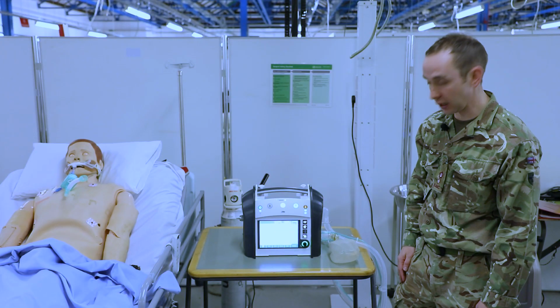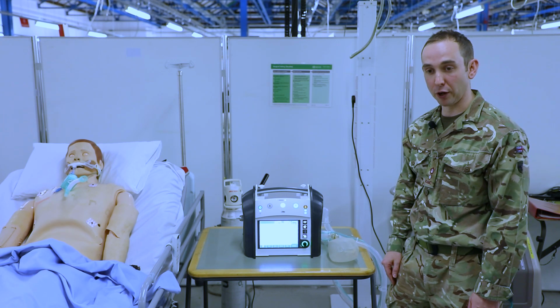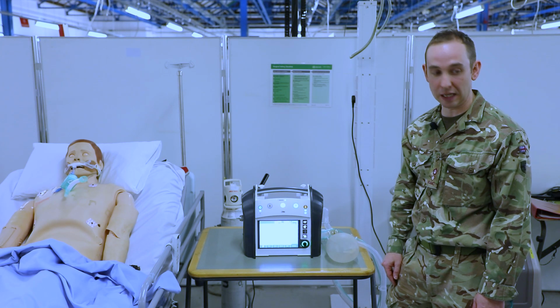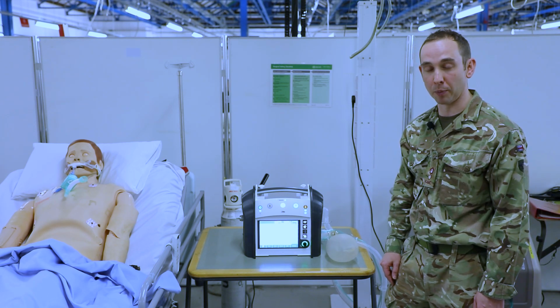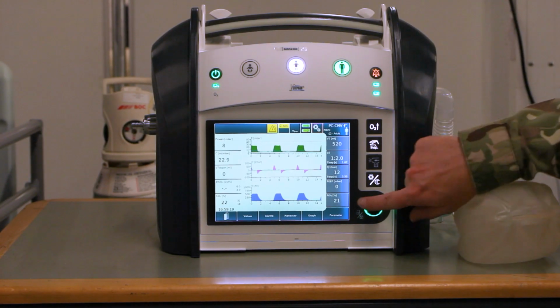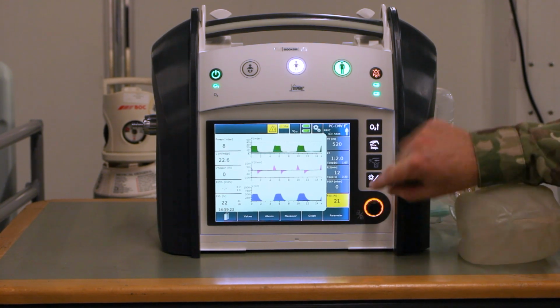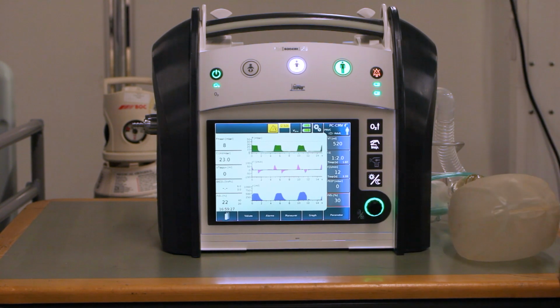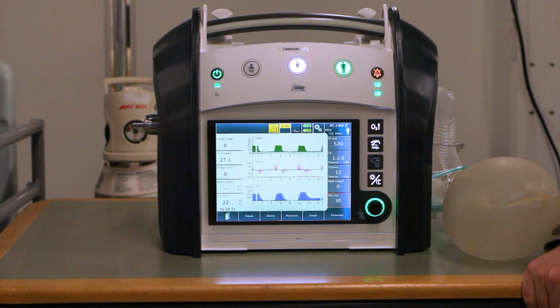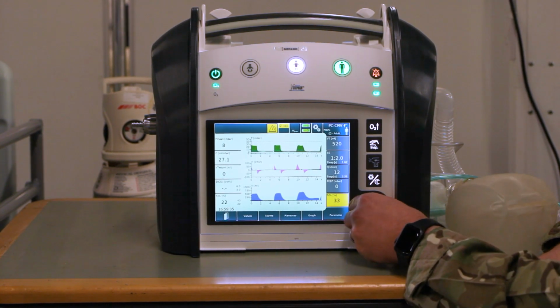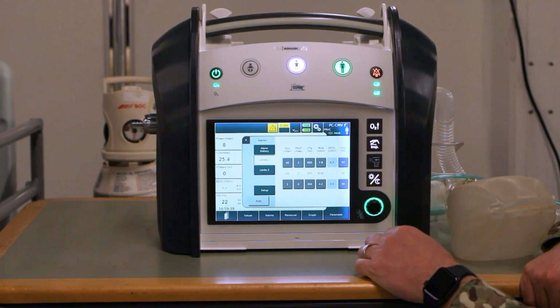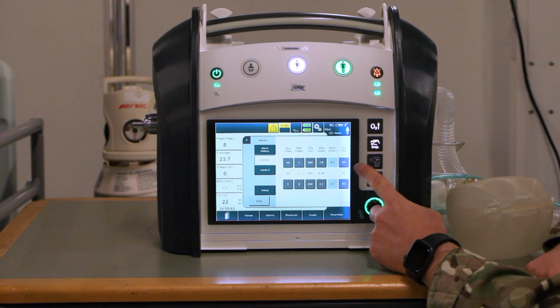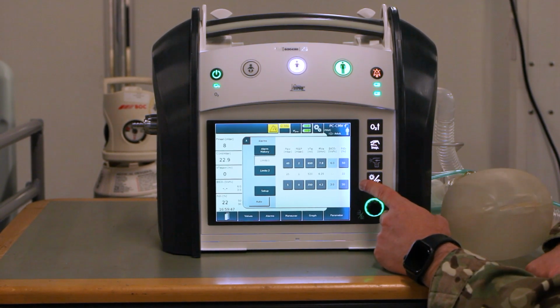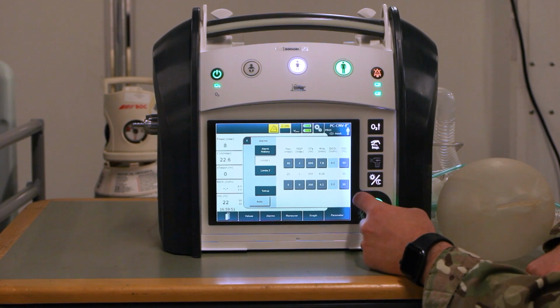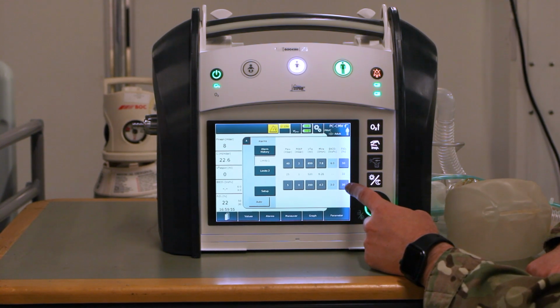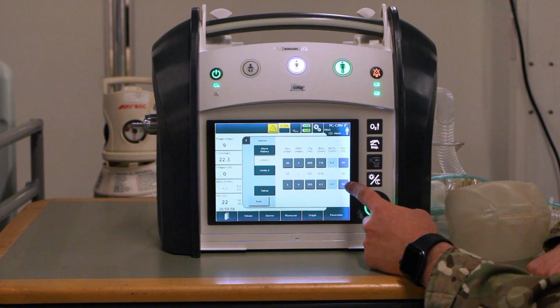So when in low pressure oxygen mode, a key bit of information to remember is that your FiO2 delivered is determined by your oxygen flow through the ventilator, either from your oxygen concentrator or from your cylinder via bubble tubing. However, in this circumstance, the FiO2 still shows on this side. If you change this, it does not change what oxygen is being delivered to the patient. What it does do is change the alarm limits that are set on the machine. If I set this to 40% and then click on the alarms, it is noticeable that the upper limit has been set 10 above the setting I have set, so it's now set at 50 and 10 below at 30. It is appropriate then to set your alarm limits around what FiO2 is desired to be delivered from your oxygen concentrator or oxygen cylinder via bubble tubing.